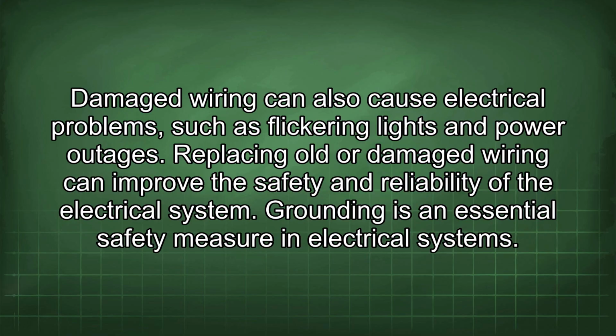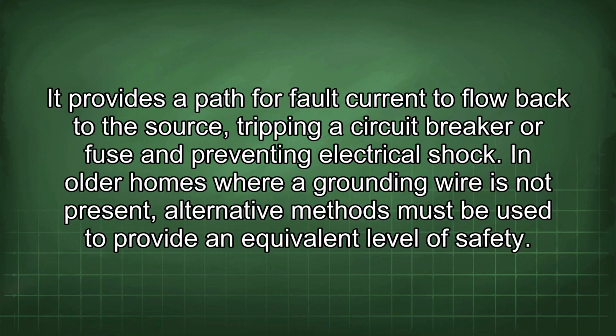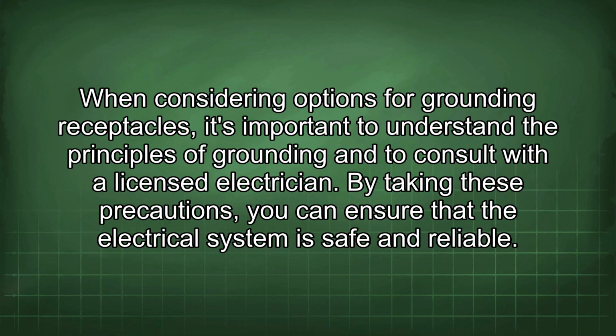Grounding is an essential safety measure in electrical systems. It provides a path for fault current to flow back to the source, tripping a circuit breaker or fuse and preventing electrical shock. In older homes where a grounding wire is not present, alternative methods must be used to provide an equivalent level of safety. When considering options for grounding receptacles, it's important to understand the principles of grounding and to consult with a licensed electrician. By taking these precautions, you can ensure that the electrical system is safe and reliable.